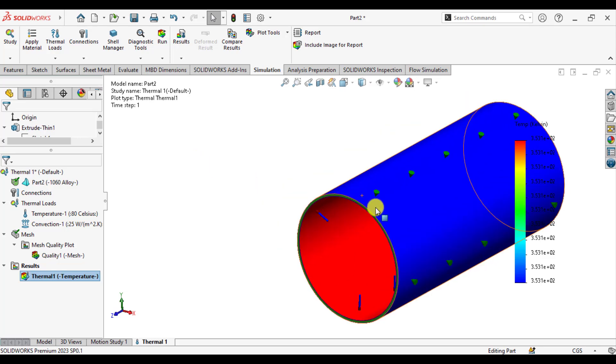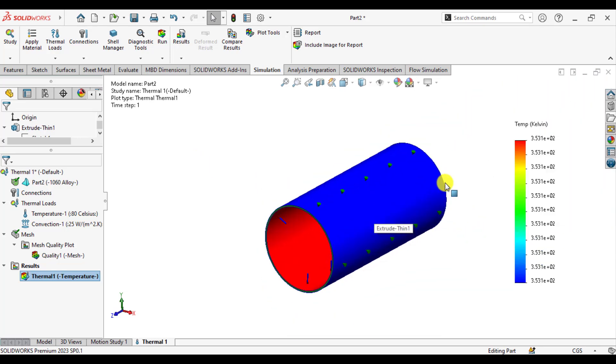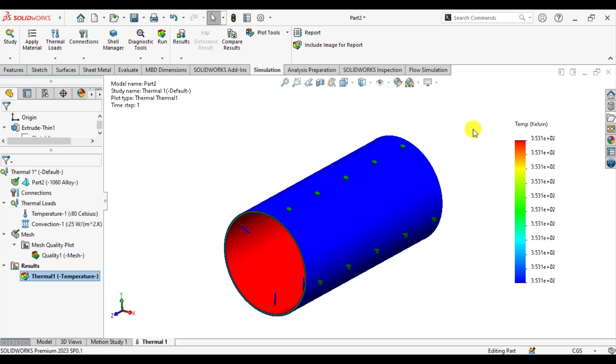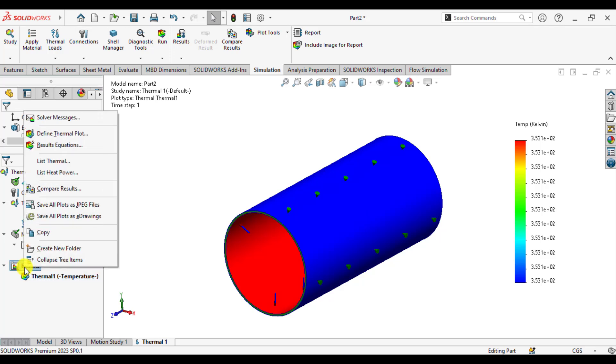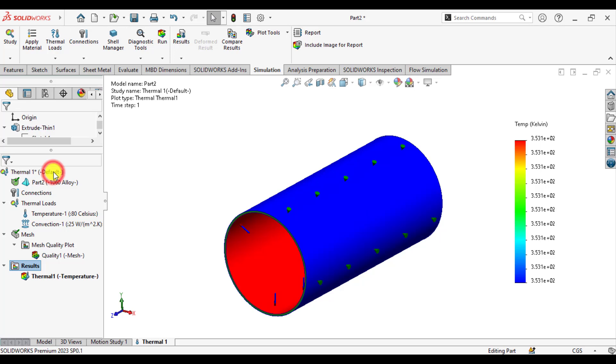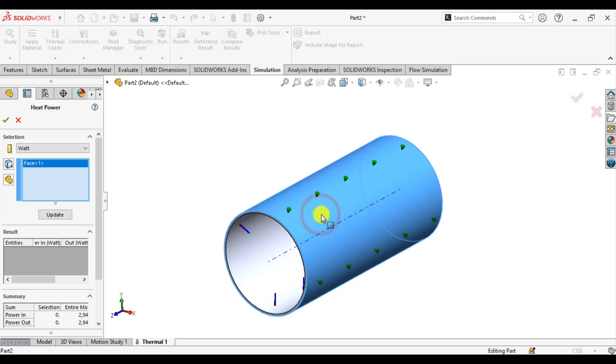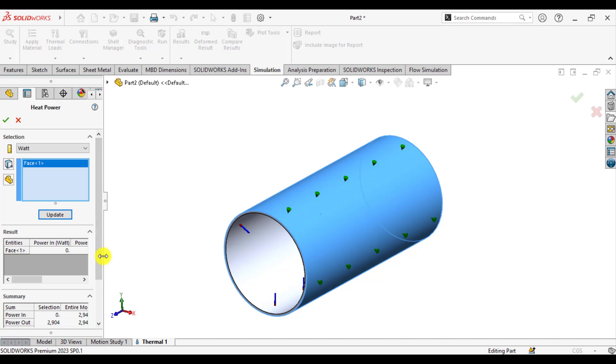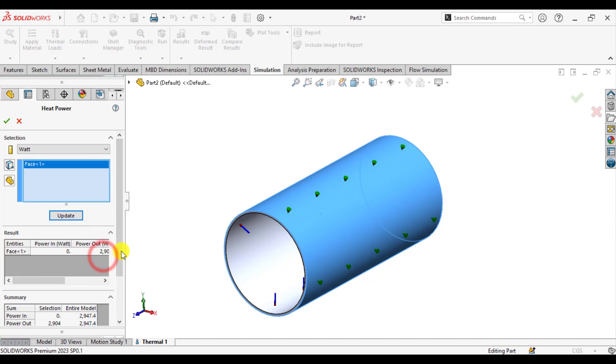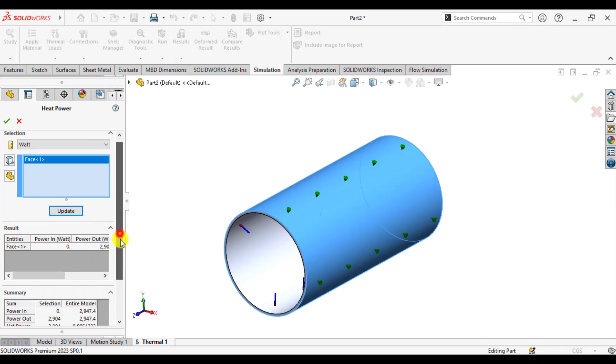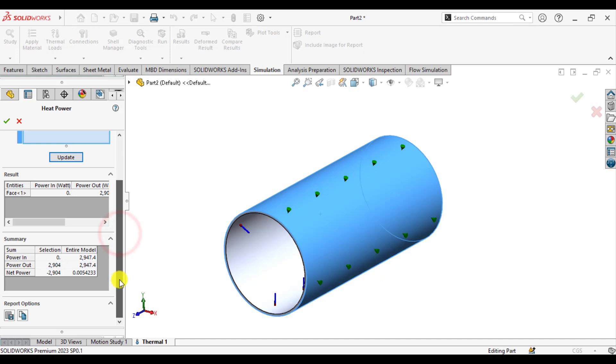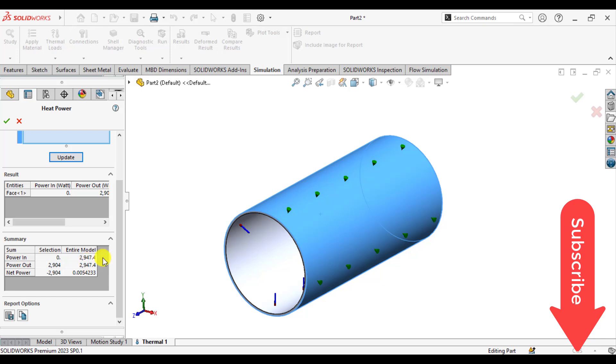Here you can see that our solution has been completed. In order to calculate the heat loss, just right-click under results and click on heat power. Then select the outer surface of the pipe and update. You can see that total heat loss from this hot water pipe is about 2947.4 watts.